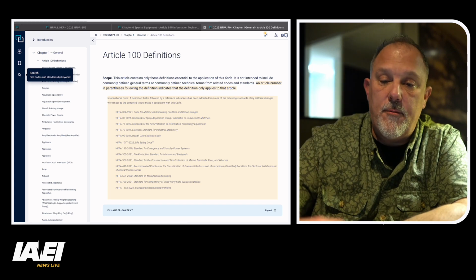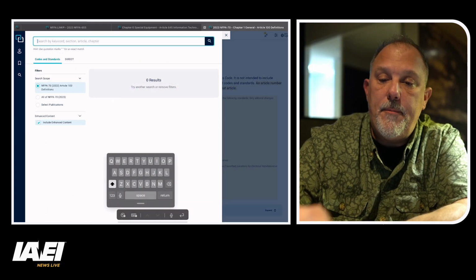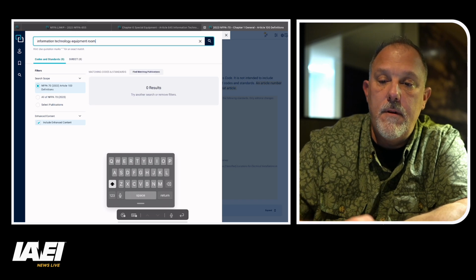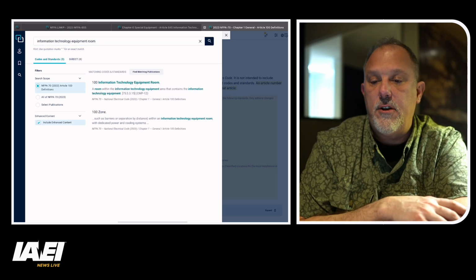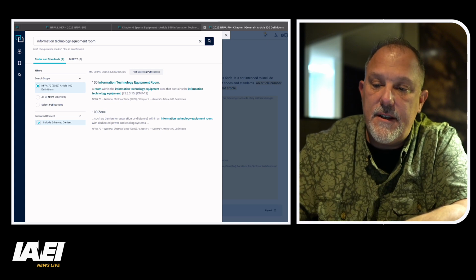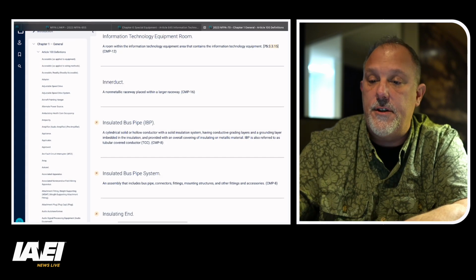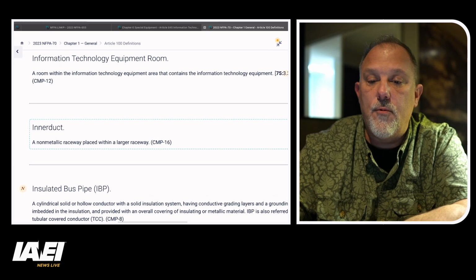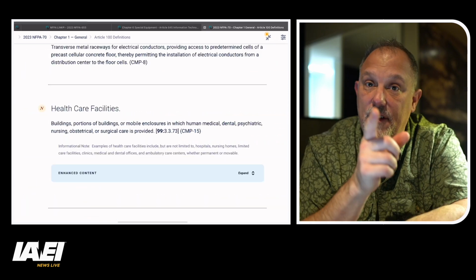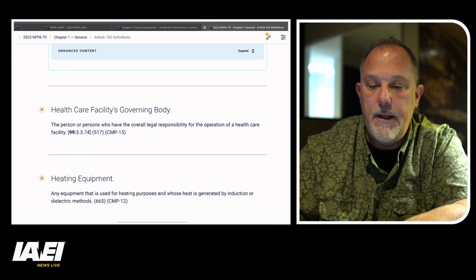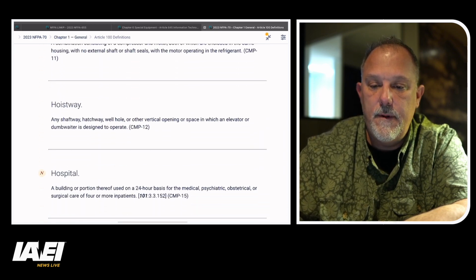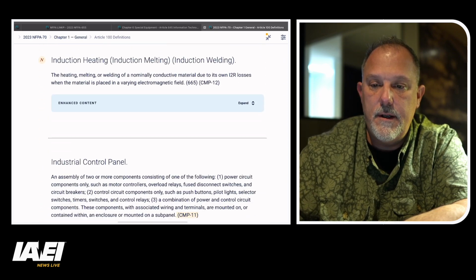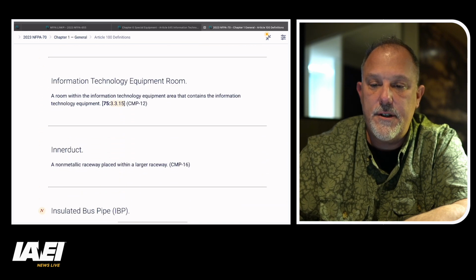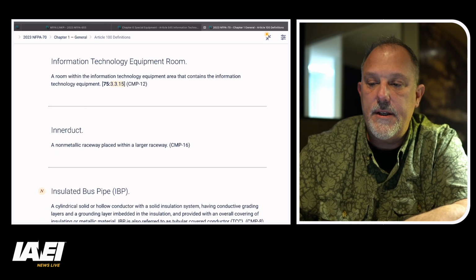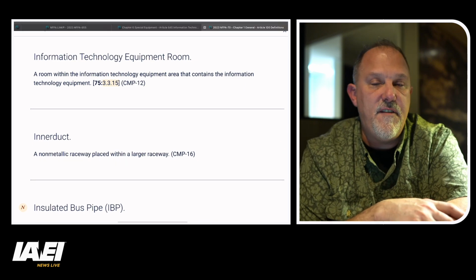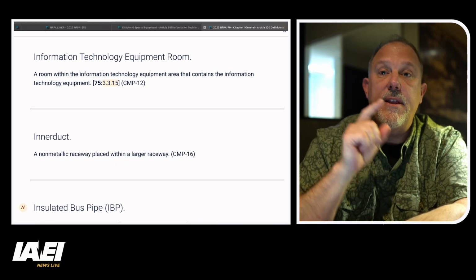So Article 100, I'm going to search, and I'm going to paste, and I'm going to search for information technology room, and it is a defined term, so that's good to know. And it says a room, and it's out of NFPA 75, which tells me, I hate when it does that. Where is information? I wasn't touching it. You saw that. Equipment, there it is.